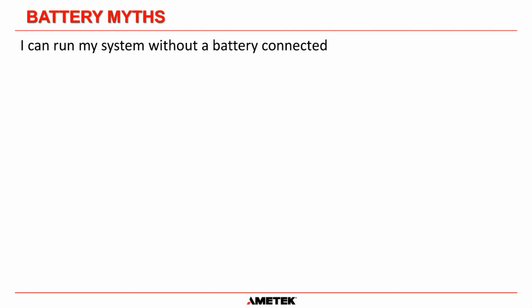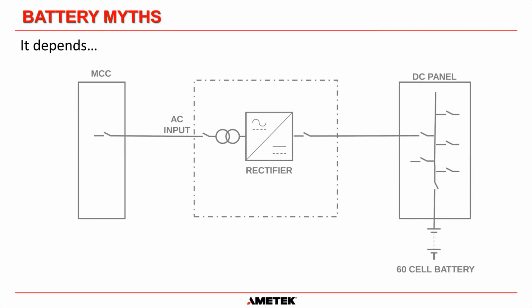On a UPS, in most cases, that is true, although there are some older AMETEK UPSs where, if you open the battery input breaker, it will shut the inverter off and transfer to bypass. But what's of more concern is a DC system, whether it's for a switchgear system or something similar. Here is the standard drawing for a DC system.